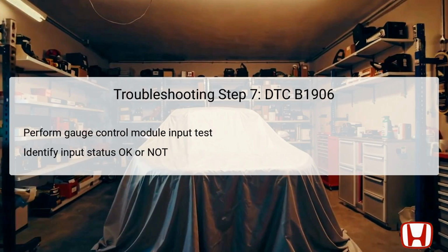Executing the input test on the gauge control module is fundamental in this 7th troubleshooting step. Here, you must determine whether all inputs are functioning appropriately. If all inputs report okay, this suggests that the gauge control module may not be at fault and indicates that you can proceed to the next diagnostic step.